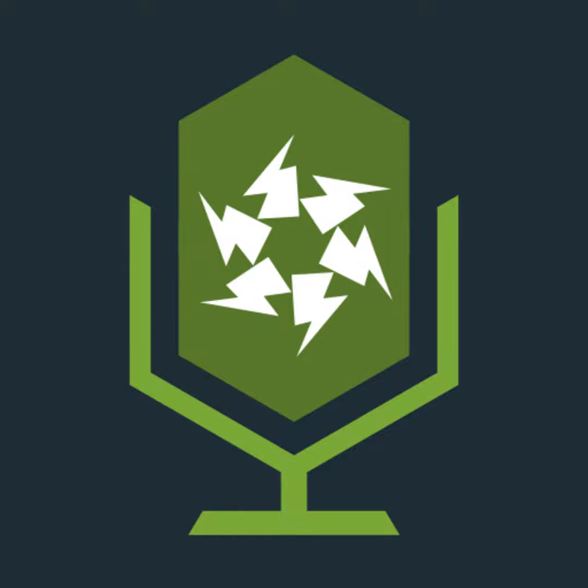So we have the 4 20 amp circuits. We take 1 20 amp out, leaving us with 3 20 amp circuits, which is 60 amp, and we do half of that, which is 30 amp, and we add that 30 amp back to the 20 amp, 50 amp. Okay, this is diversity with power circuits. Just going back to this one, remember earlier on we said it was 37.5 amp, wasn't it? If we did it all on one circuit. By applying diversity, we have managed to drop that a little bit. So going on a single circuit basis for each of those has worked out better.